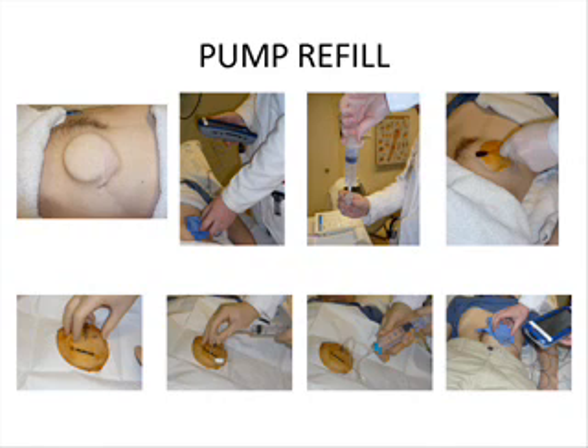So the second picture shows you that we talk to the pump just to interrogate and see how much we expect. We then draw up the medication, which is what that big syringe is. We then clean off the area, sterilize the area with betadine. And then we align a template over the pump. And this template I'll show you here looks like this. So we lay this over the pump in a particular orientation, and we need to really try and hit the right target right in the middle. That helps us find the reservoir septum. We then withdraw the medication, switch syringes, infuse the new medication, and then we reprogram the pump to tell it that we've refilled it.